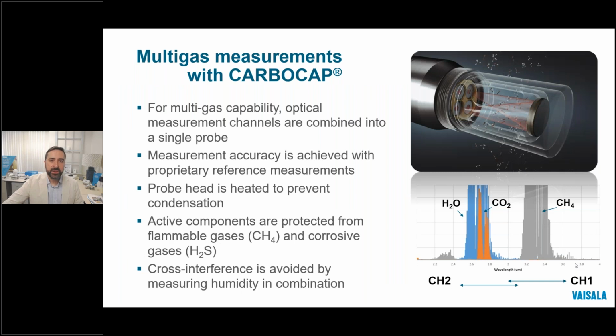The way they work is with our patented CarboCap non-dispersive infrared sensors, or NDIR, which are an evolution of the NDIR sensors that you might be familiar with. What sets these apart are a few key components that deliver more long-term stability than any other NDIR sensor on the market. First, we use our own solid-state light source that does not dim in the way others do, which has a lifespan of over 10 years. And that's compared to a 1 to 3 year lifespan of others.